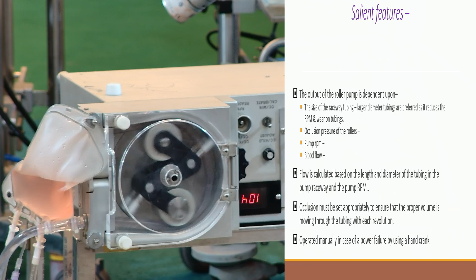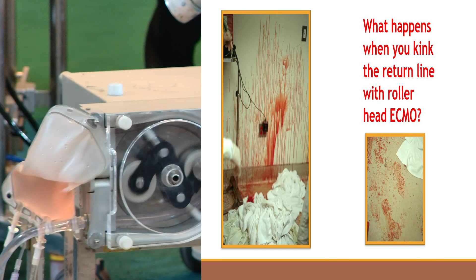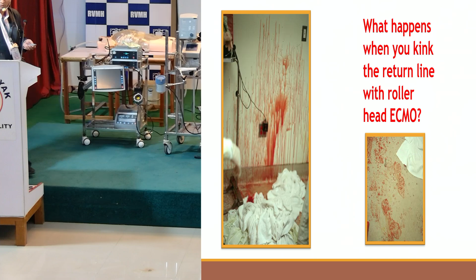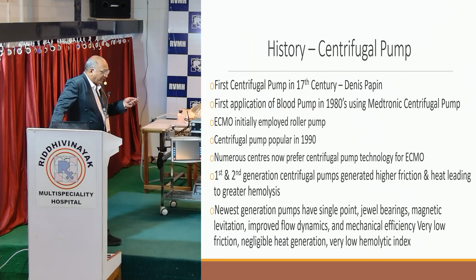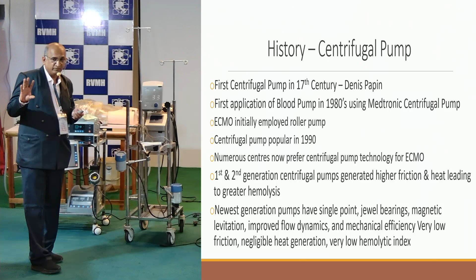Fine. So advantages and disadvantages of roller pump. Okay. And this is what happens if you clamp the return line of roller pump. You have blood all over your ICU or OT and everywhere. Okay. Now we came to centrifugal pump. Again, centrifugal pump, basically as I told you, it's not a positive pressure pump. It creates a vortex. It creates a vacuum. It creates a vortex, and thereby it sucks the blood and then it pushes the blood forward.